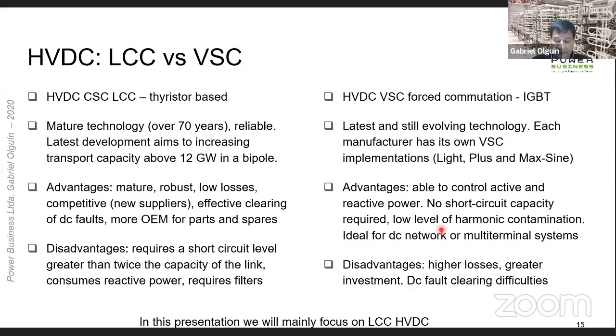However, LCC has some disadvantages, such as the need for reactive power compensation for up to 60% of the rated converter power, the need for a minimum short circuit level, and the need for AC filters to filter out the AC harmonic current. On the other hand, VSC uses IGBTs, which are capable of switching at high frequency. This is the latest and still evolving HVDC converter technology. It offers some powerful system advantages, such as independent control of active and reactive power, no need for reactive power compensation, eventually no need for AC filter, small footprint, and eventually black start capability.